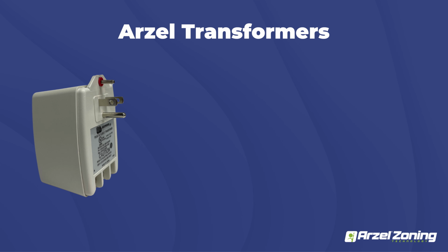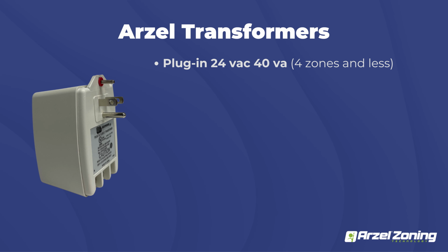So with any of our panels, it's also going to ship with a transformer. If it's 4 zones or less, it's going to come with a plug-in style transformer pictured on the slide right there. It's a 120 volt transformer. You're going to plug that right into any standard wall outlet, and then that's going to provide your 24 volts to your panel. The transformer itself has an auto resetting fuse built into it. So if there's ever a short between the panel and the transformer, it's going to drop out your secondary voltage until that short is fixed. And then it's going to regain that secondary voltage on the transformer.